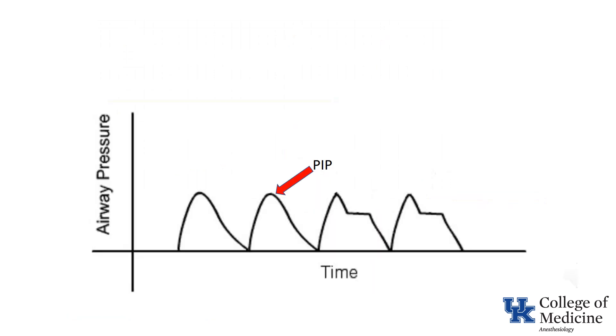Now back to the airway pressure-time curve. As previously noted, this graph shows the inspiratory pause being added at the end of inspiration with an apparently unchanged fresh gas flow rate, as evidenced by the fact that the peak inspiratory pressure is unchanged after the addition of an inspiratory pause. Note that with the addition of the inspiratory pause, a new airway pressure — the plateau pressure — can be determined. This is commonly measured immediately before the ventilator cycles to exhalation.